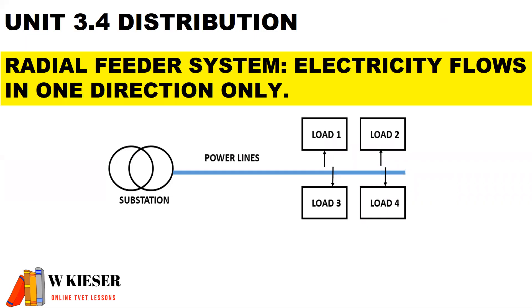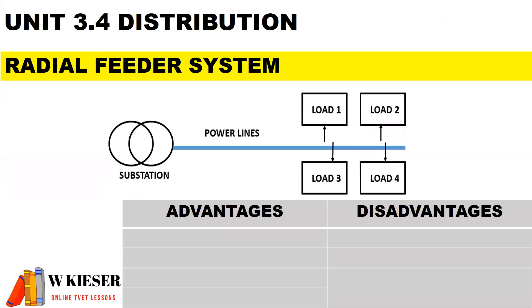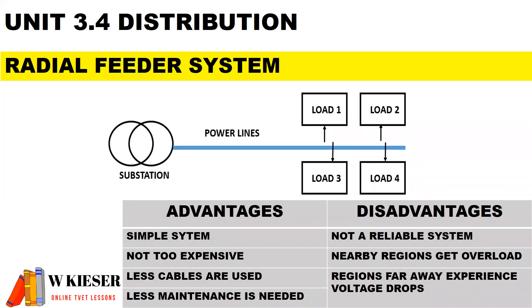For the radial feeder system, electricity flows in one direction only from the substation. There is one single power line supplying different loads, which could be industrial or commercial consumers. The advantages are that it is simple, not too expensive, less cables are used, and less maintenance is needed. However, the disadvantages are that it is not reliable, nearby regions get overloaded, and regions far away experience voltage drops.